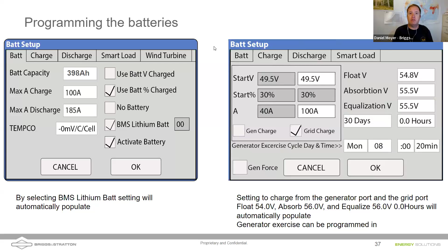So what we can use, using a smart load tab, is put some luxury items on that gen port and have a smart load output so those loads come on automatically in the afternoon. I always tell homeowners, go do your laundry, go do the dishes, start using that power when the batteries are full. We can put an EV charger or other loads on that smart load tab. Using that tab in this whole home backup configuration is really powerful, and excuse the pun, it can really work and help leverage things so the homeowner's behavior doesn't necessarily have to change as much.